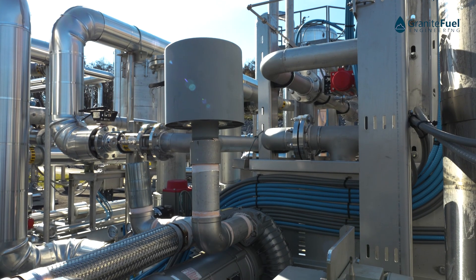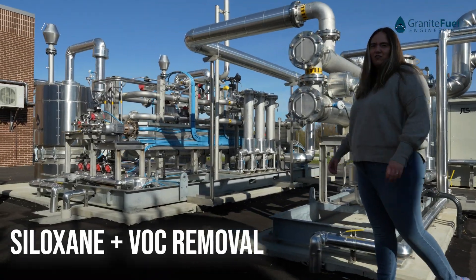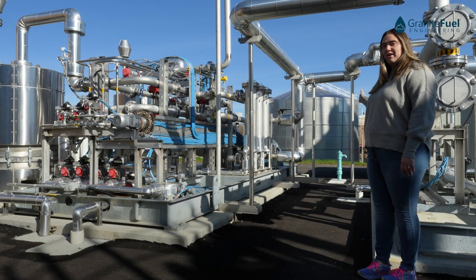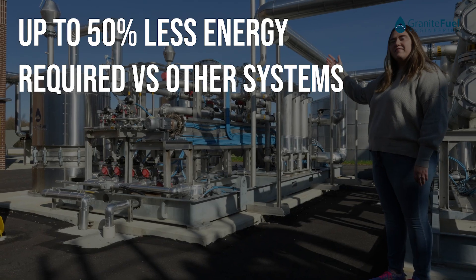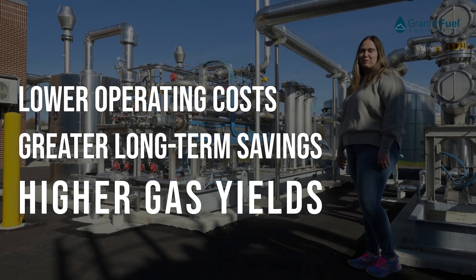Once the gas leaves our knockout tank we then travel over to our temperature swing adsorption system to remove siloxanes and VOCs. The gas leaves this knockout tank at about 40°F and is sent to a series of particulate filters before it heads into our vessels and then ultimately back to this dehydration system to be reheated before it's used in downstream equipment.